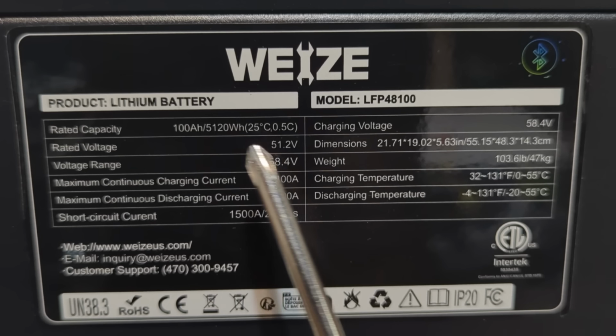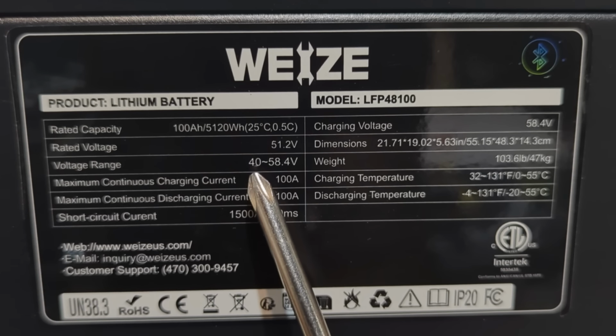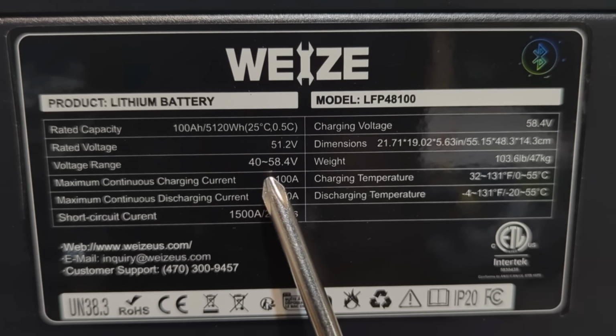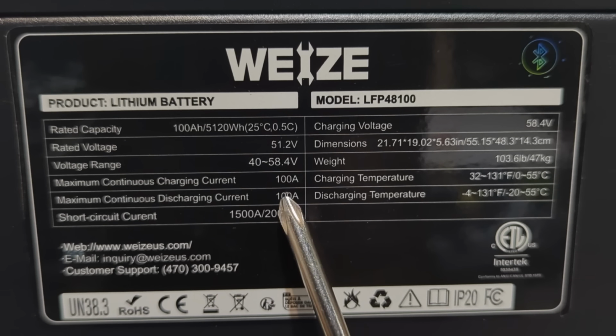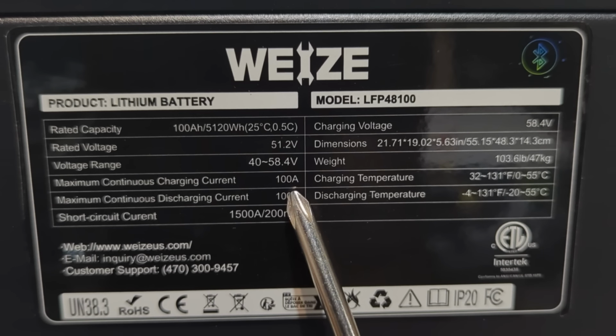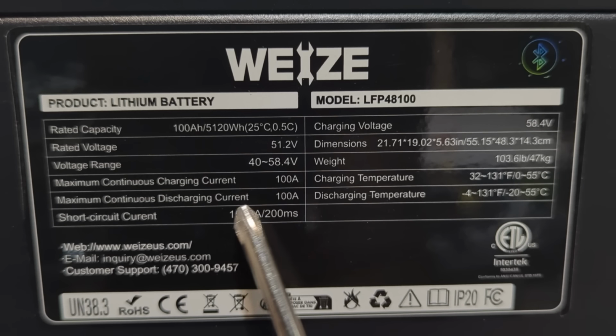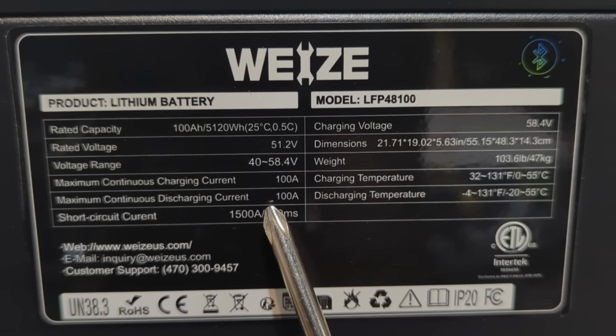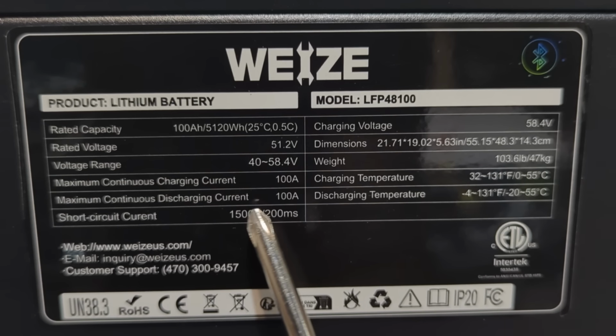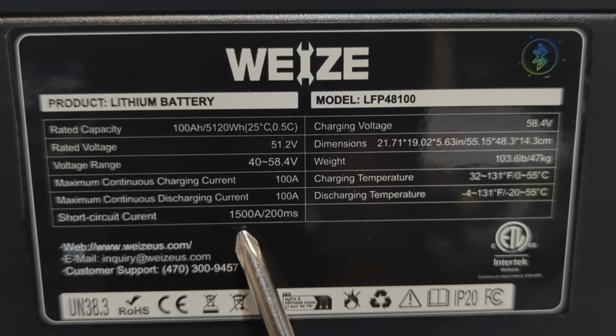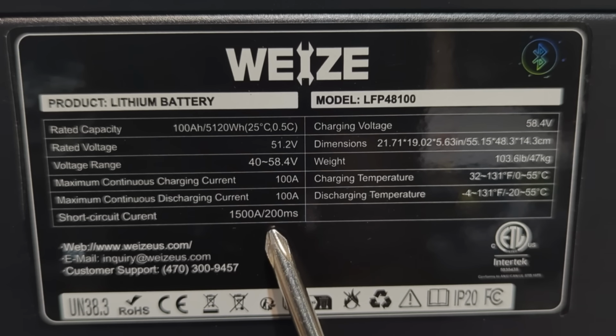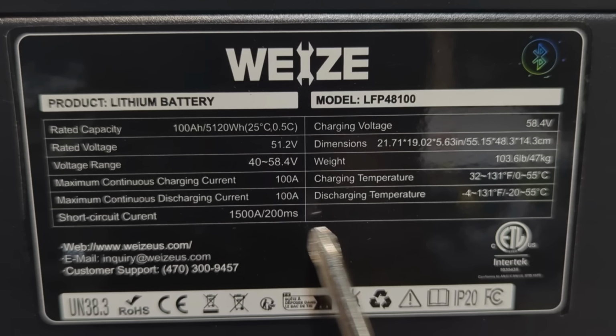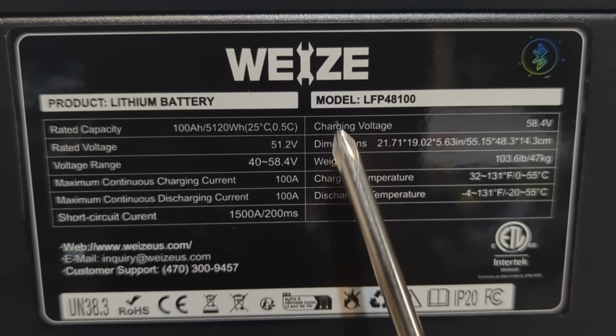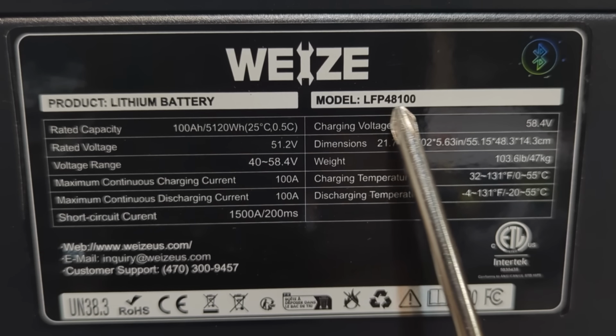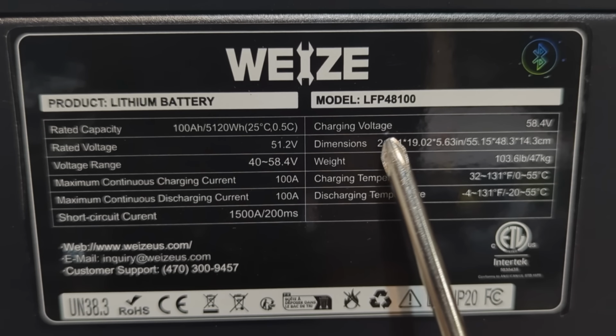It's completely depleted at 40 volts and it's fully charged at 58.4 volts. Maximum continuous charge and discharge current is 100 amp. For the short circuit, the battery can spike up to 1500 amp if there's a catastrophic direct short circuit. If that ever happens, the BMS will detect the danger and shut off output within 200 milliseconds to prevent a fire or explosion. Here is the model of the battery, LFP 48100.